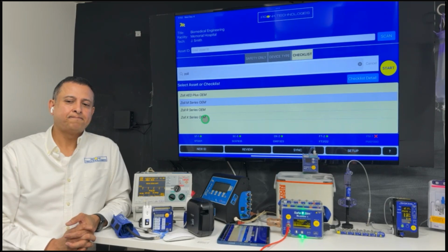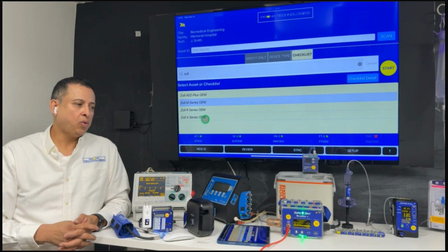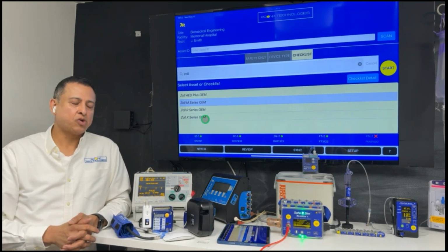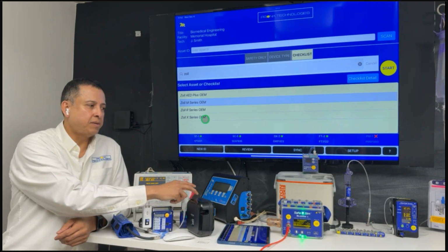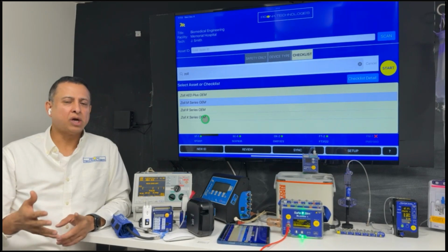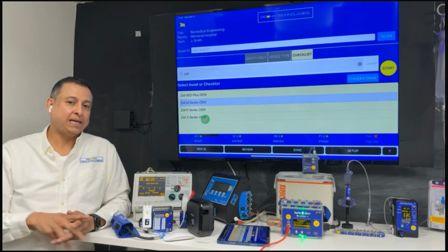And then someone asked, would an old SimCube SC5 work with this? Yeah, so we try to design all of our products so that they're upgradable. And so we try to maintain that with these designs. We know there's a lot of happy customers with our products. And so you do have the ability to upgrade all of our SimCubes or OxSims, even if you have the prior generation OxSims, infusion pump analyzer, safety analyzer. We would just need to look at the serial number and confirm that the hardware is compatible. As long as the unit's around 10 years or less, then they can be upgraded.